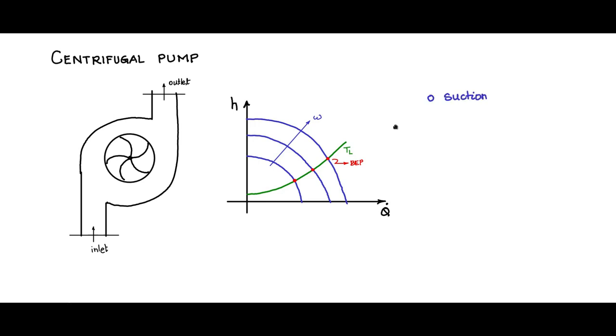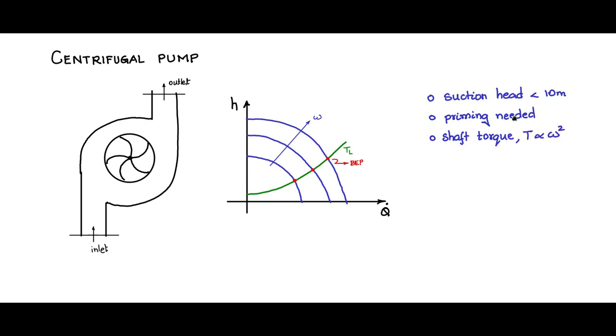Some important points: suction head should be less than 10 meters, because by suction you cannot exceed 10 meters; in practice, less than 6 meters is achievable due to friction losses. Priming is needed — you must fill the centrifugal pump with water first, then switch on the motor. The shaft torque as seen on the motor shaft is proportional to omega squared. The head is dependent on flow rate and speed.